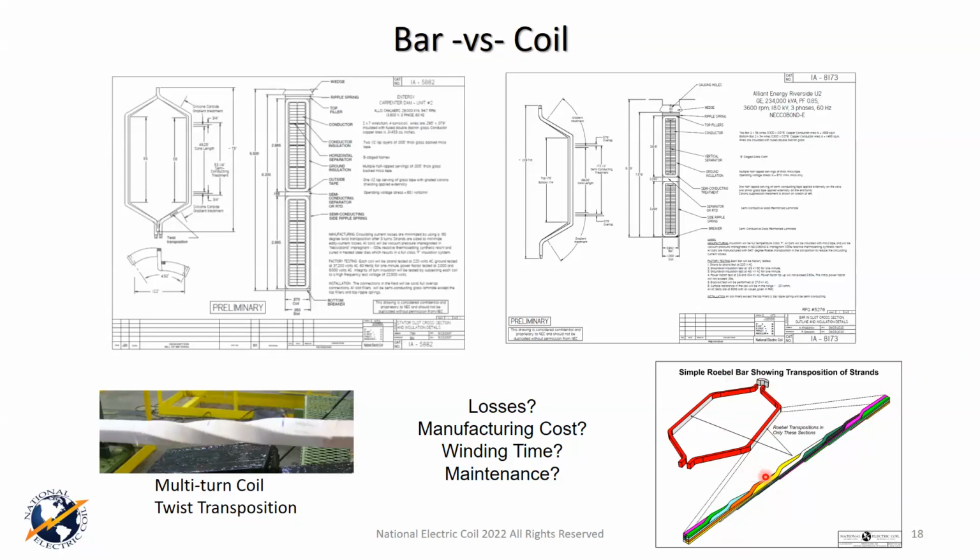All right, and then there are a variety of different Roebels, and they have to do with the degree of how it's circulating around that coil. 360 is very common. Another common one is 540. Another common one is 720, meaning it went around the coil twice in one length of that bar, okay? And then there's also a 900, which is becoming more prevalent today.